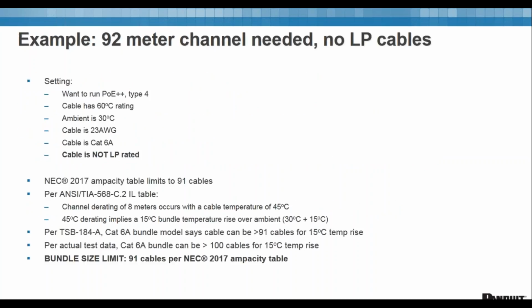So in this example, you need a 92 meter channel and you're not using an LP cable. A few details: you're running Type 4 PoE, the cable is 60 degree rated, ambient is 30, the cable is 23 gauge, and it's 6A, not LP rated. With that information, the National Electric Code limits you to 91 cables, referring to the ampacity.